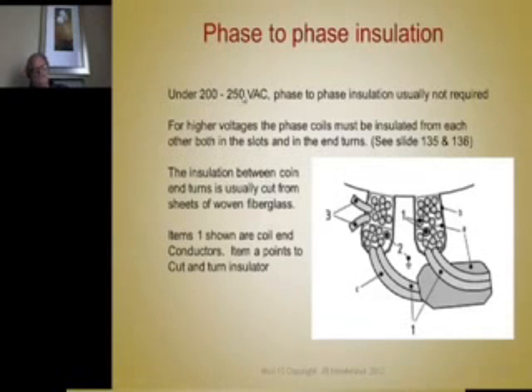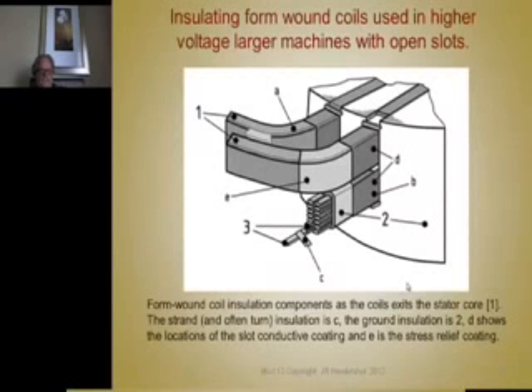It's probably between 100 and 250 volts. You only need phase insulation in the end turns. You probably don't need them in the slots. So there's the insulation between the phases and the slots. To do this in the end turns, you take a sheet of this insulation fiberglass and you slip it between the phases, so you have all of these lapped all the way around the stator, and then you trim them with the scissors. You have to be careful trimming them with the scissors so that you can form and lace these end turns and keep them as small as possible. They should be pushed in there, and this side here touches right up against the stator core. So there's no chance of any of these creeping down and touching any of those. It's hard to show why you need to do that from a picture like that.